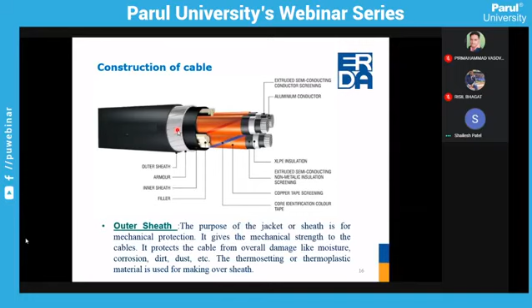Correct? After that, the last layer, that is the outer sheath. This outer sheath provides protection to the armor and other components of the cables. If we don't provide this outer sheath and just lay the cables with armor, then the armor will corrode very fast. Even within 1 month, it will be corroded because supersaturated air will be there in underground cables. So the armor material will be contaminated and corroded, it will become brittle, and it will not function properly during short circuits, correct? So to protect against all these conditions, this outer sheath is required, and normally these outer sheaths are of PVC material, correct? So this is the basic construction of the cables: conductor, semiconducting layer, insulating material, semiconducting layer, copper screen, color coding tape, filler, inner sheath, armor, and outer sheath.